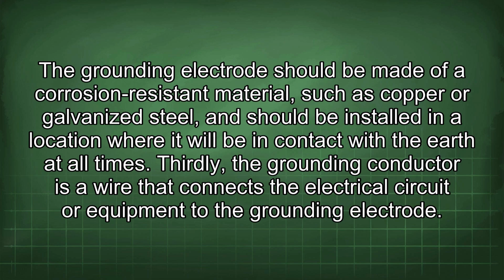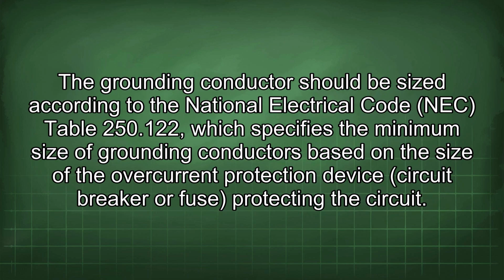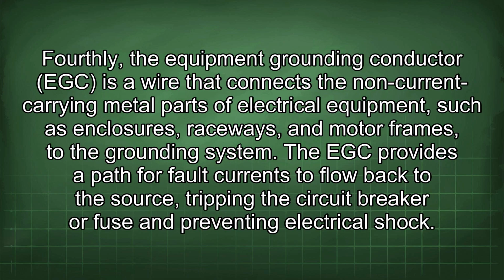Thirdly, the grounding conductor is a wire that connects the electrical circuit or equipment to the grounding electrode. The grounding conductor should be sized according to the National Electrical Code (NEC) Table 250.122, which specifies the minimum size of grounding conductors based on the size of the overcurrent protection device, circuit breaker or fuse, protecting the circuit. Fourthly, the equipment grounding conductor (EGC) is a wire that connects the non-current carrying metal parts of electrical equipment, such as enclosures, raceways, and motor frames, to the grounding system. The EGC provides a path for fault currents to flow back to the source, tripping the circuit breaker or fuse and preventing electrical shock.